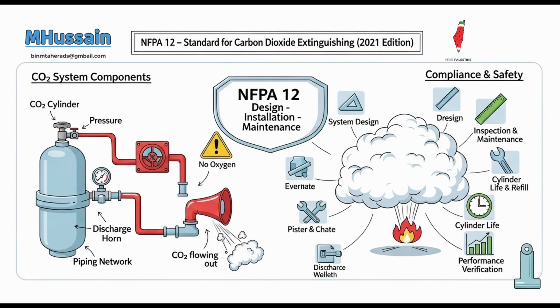For cargo spaces, excluding vehicle spaces, the design is based on 1 pound of CO2 per 30 cubic feet of gross volume. The initial discharge quantity is calculated based on the net volume, accounting for the cargo itself. Net volume, okay. And critically, additional CO2 must be released as needed to maintain fire suppression, because fires in cargo spaces might not be fully extinguished by the initial discharge and could require intermittent releases until the vessel reaches port. Cargo fires might need multiple shots of CO2. Exactly. Clear instructions for this complex release procedure must be prominently posted.